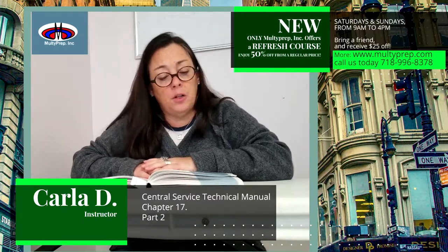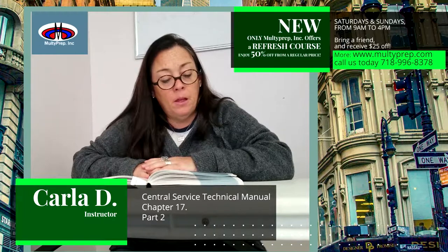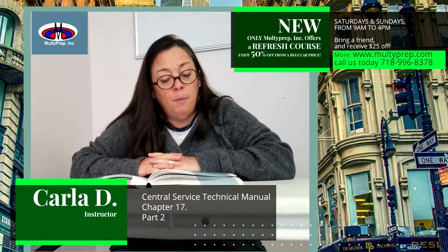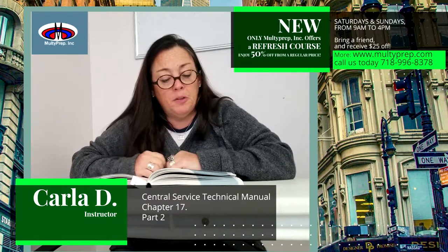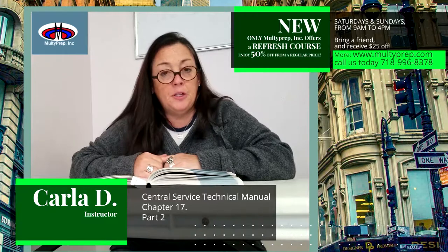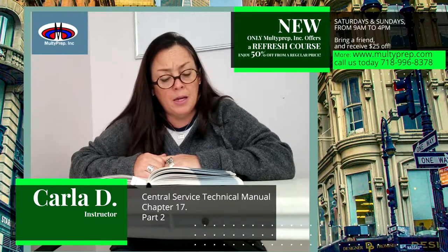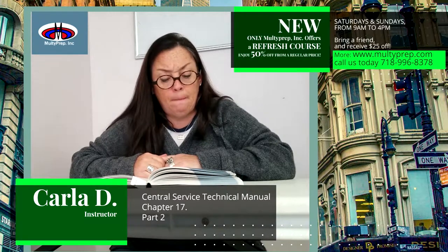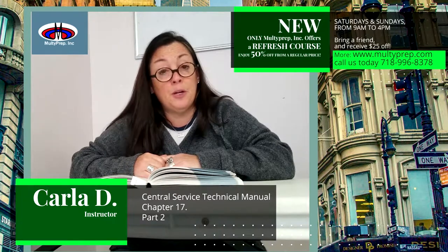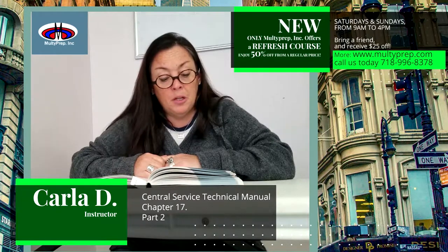Ethylene oxide sterilizers. Biological indicators and process challenge devices. Biological indicators are the most acceptable means of providing quality assurance monitoring for ETO sterilization. Like biological indicators used in steam sterilization, an ETO BI has a carrier that has been inoculated with a known population of a microorganism that is highly resistant to the sterilant. The microorganism of choice for ETO is the Bacillus atrophaeus spore.